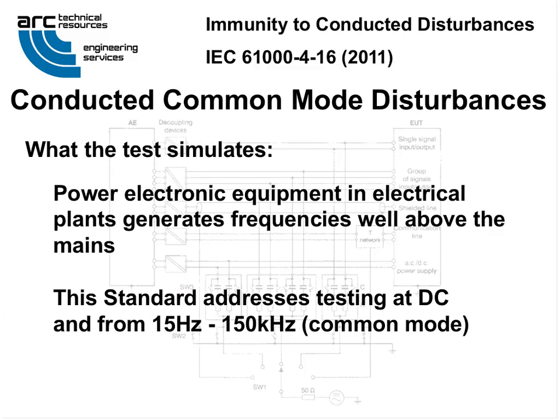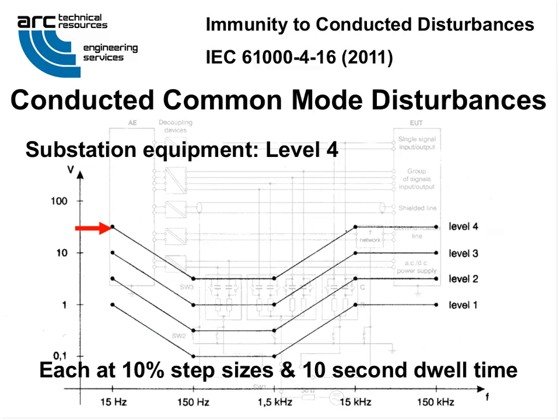Conducted common mode disturbance testing simulates electronic power equipment in electrical plants, which generates frequencies well above the mains. The standard addresses testing at DC, and then separately from 15 hertz to 150 kilohertz in common mode only. This is for external threats. That's the reason it's common mode only. This is the drive table of levels that you're supposed to deliver. Level 4 inside the substation fence, or level 3 for equipment mounted outside the substation fence.